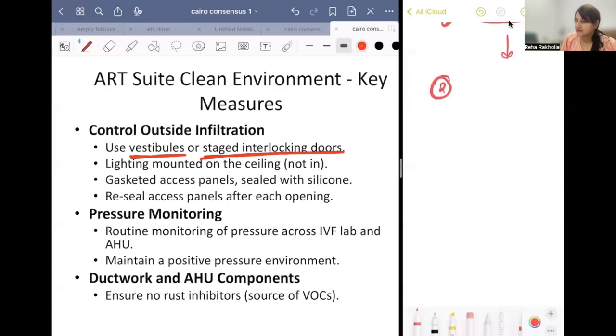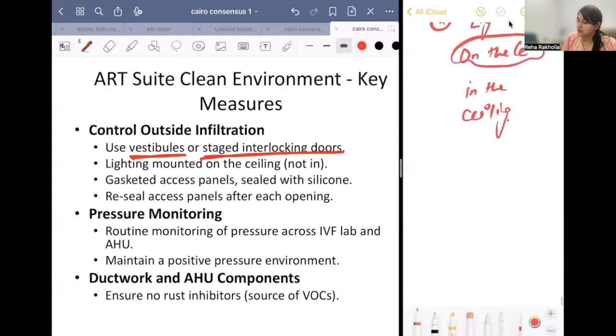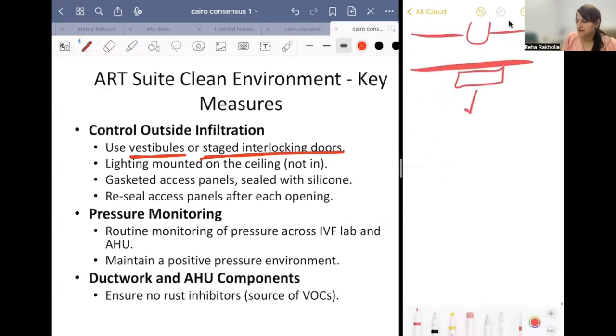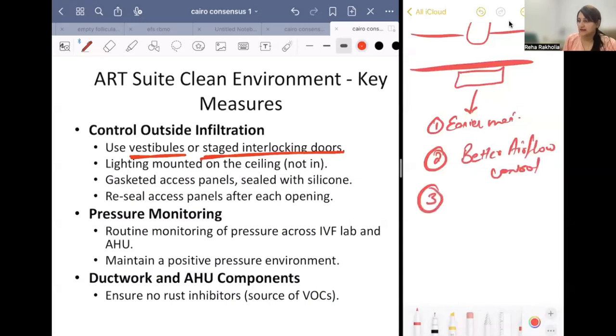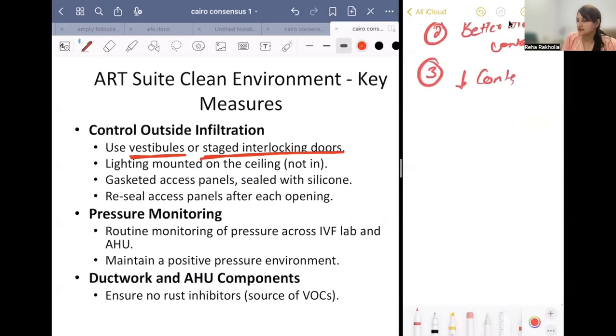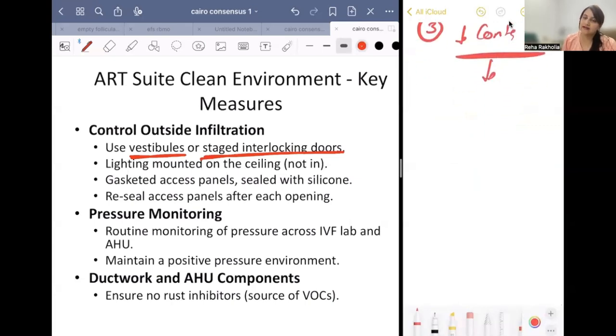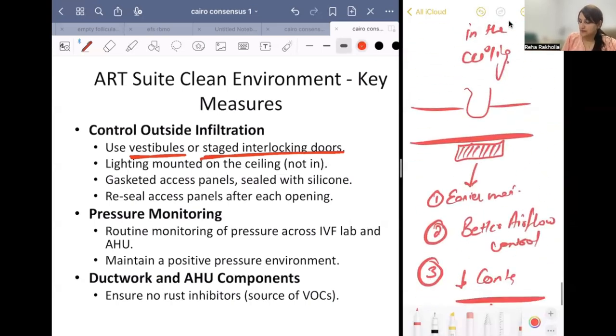Then second is lighting - it should be on the ceiling, not in the ceiling. It should not be embedded inside; it should be on the ceiling surface. This gives easier maintenance, better airflow control so there won't be any leakage of air, and decreased contamination because there is less embedded space and fewer areas where dust and contamination can accumulate. So, lighting should be on the ceiling, not in the ceiling.